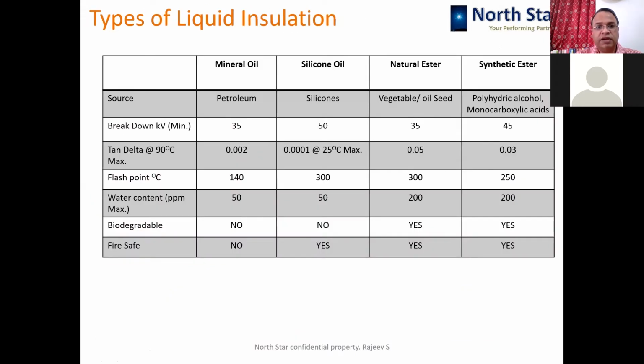Okay, so the different liquid insulations currently in use are four major types: mineral oil, silicon oil, natural ester, and synthetic ester. Silicon oil is not that popular. Mineral oil has been used for ages, so most of the transformers, rather all the transformers, use mineral oil. Now slowly the trend is moving towards natural ester and synthetic ester. We had given a dedicated program on natural and synthetic ester. Our last episode was on this topic only.